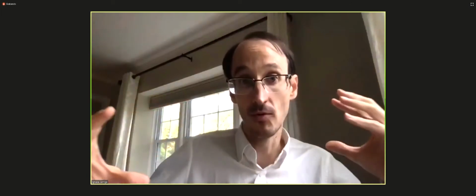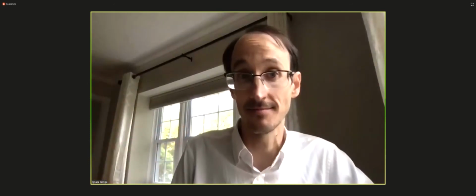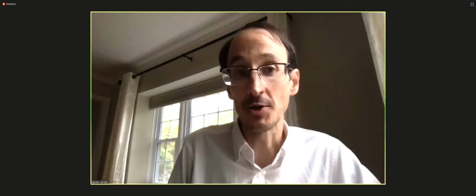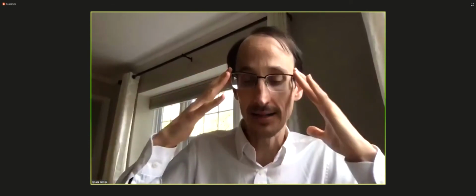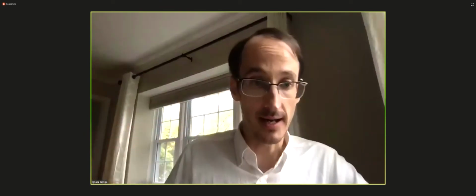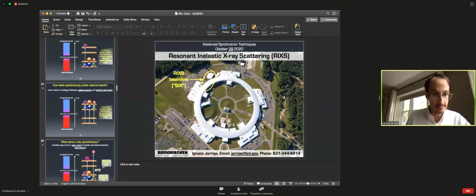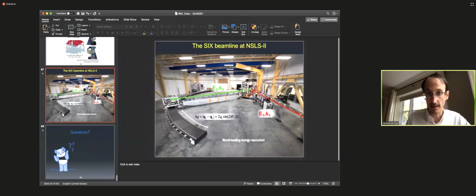When it moves, it doesn't have to be vibration free. Now, you don't want it to rattle like hell, otherwise you will lose your alignment. So for that, what we've done is the granite tracks. I can go back to this here, share screen. We have 2 granite tracks: one here, where the monochromator of the spectrometer is, and one here for the detector.